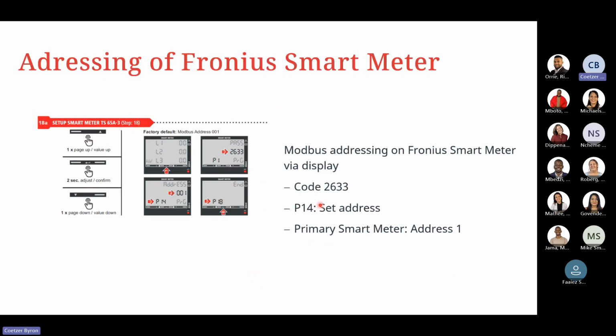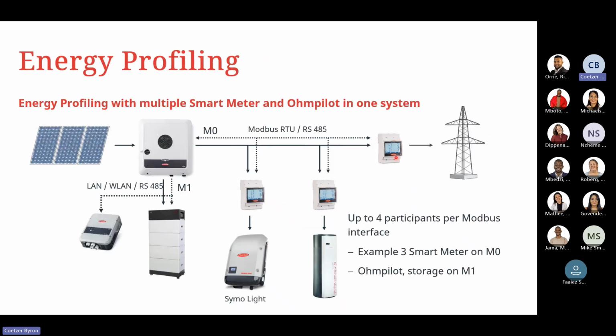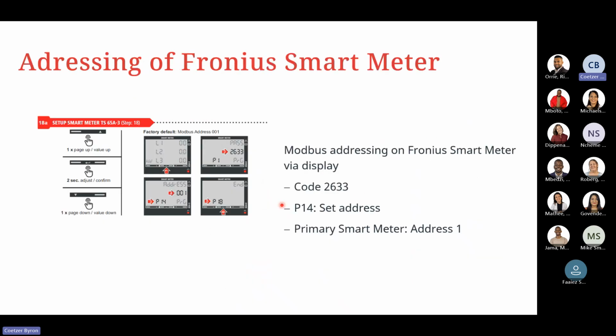So if we are using multiple smart meters, we need to do addressing of the Fronius smart meters. By default, when you receive the unit, it'll have Modbus address 001, which means it is set as a master smart meter, typically located at your main grid or feeding connection point. Any additional meters in the system we need to assign from Modbus address 2 upwards. So we'll have Modbus addresses 2, 3, and 4 available to us, which allow us to communicate correctly to the inverter and thus directly to SolarWeb for the data.